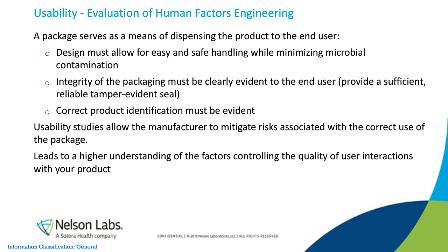Furthermore, a package serves as a means of dispensing the product. So how do I go about doing that? You need to ensure that your design allows for easy and safe handling while minimizing microbial contamination. You also need to look at the integrity of the packaging. Is it evident? Do you have a tamper evidence seal? And then is it correctly identified? Is the labeling correct? These studies will allow you to mitigate any risks with the correct use of the package while leading to higher understanding of the factors that control the quality of the user's interactions with your product.